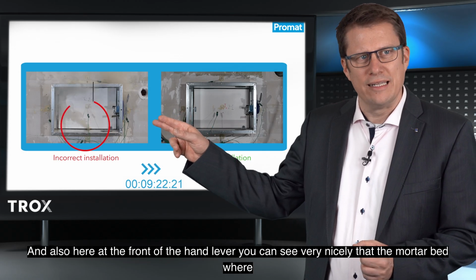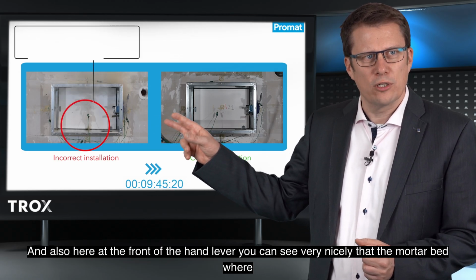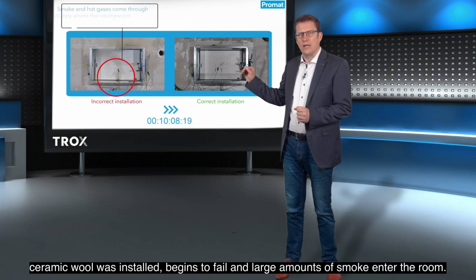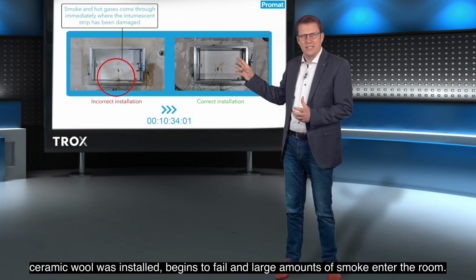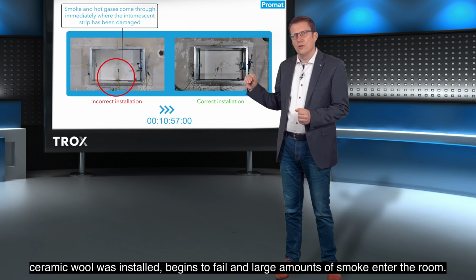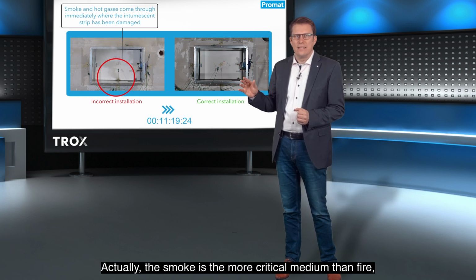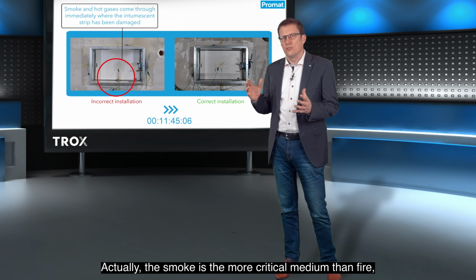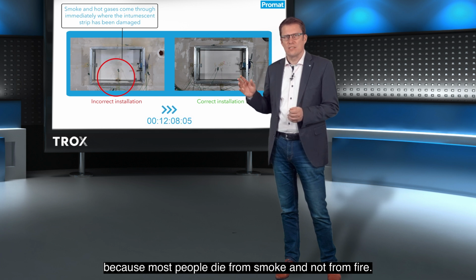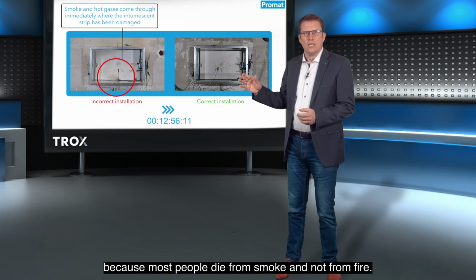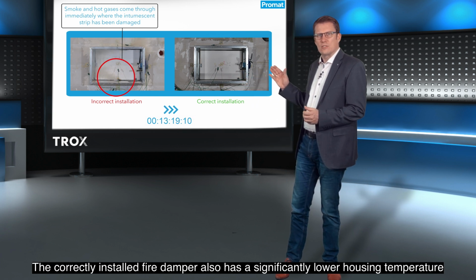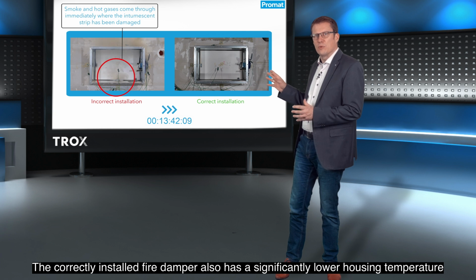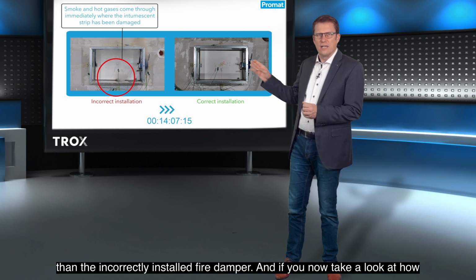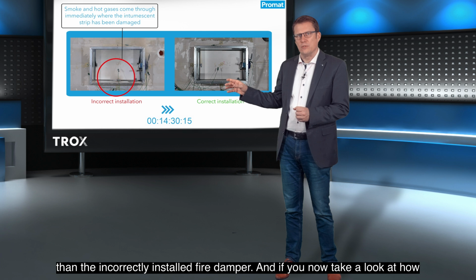And also here, at the front of the hand lever, you can see very nicely that the mortar bed where ceramic wool was installed begins to fail and large amounts of smoke enter the room. Actually, the smoke is the more critical medium than fire, because most people die from smoke and not from fire. The correctly installed fire damper also has a significantly lower housing temperature than the incorrectly installed fire damper.